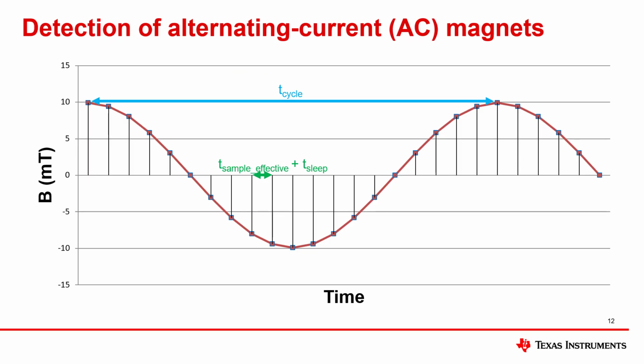AC magnets not only affect current transformers, they can also affect shunt and Rogowski coil current sensors. To detect AC magnets, a 3D linear Hall sensor can also be used. Detecting AC magnets requires a fast enough effective sampling period and a small enough sleep time to properly capture enough samples along a cycle of the AC magnet waveform, as shown in this picture.